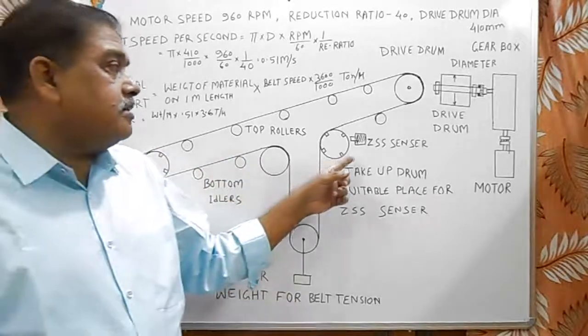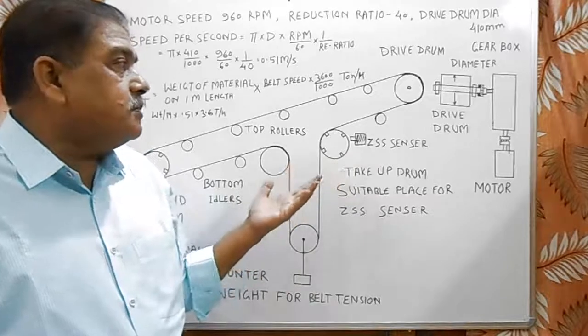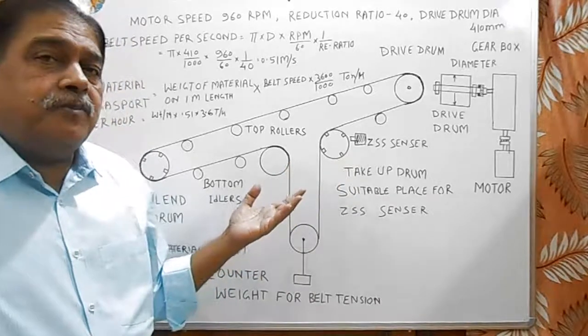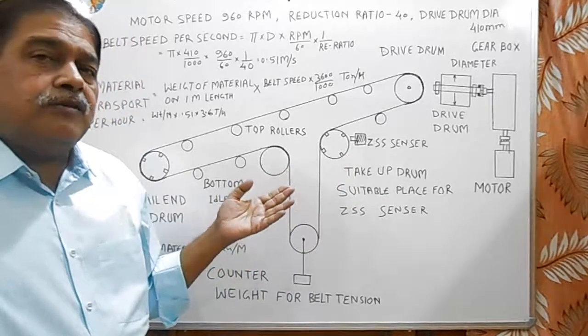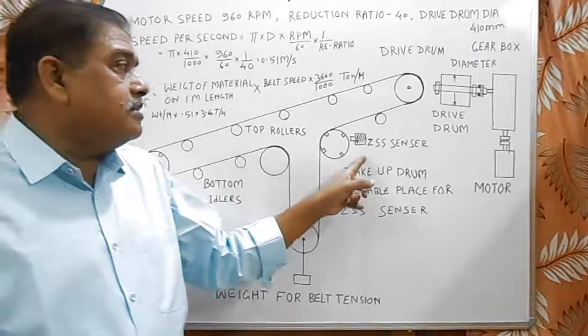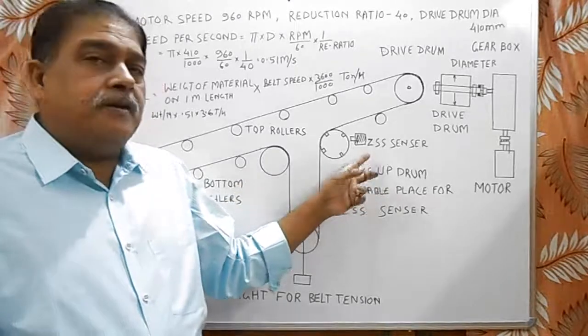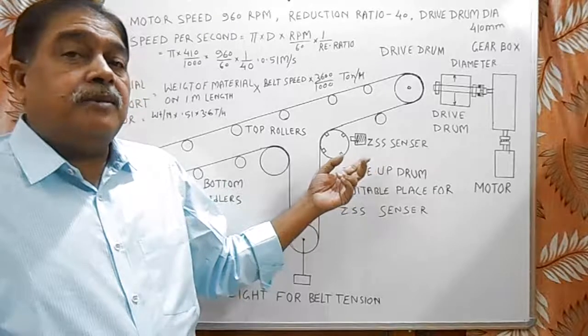And this ZSS is used to sense speed of belt. Whenever the speed of belt decreases below 75 percent of speed, this ZSS gives a signal that belt speed is slow or belt is snapped out.